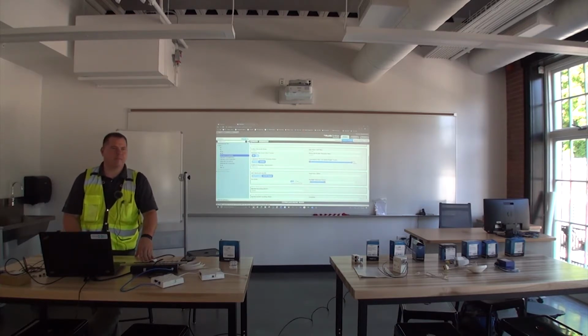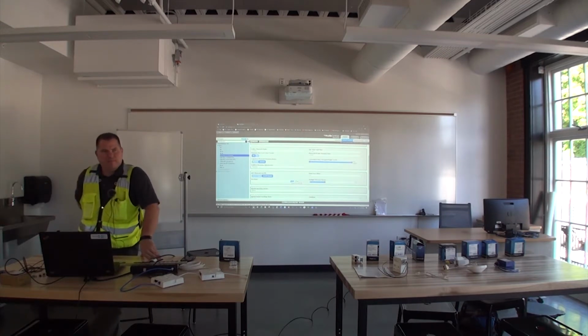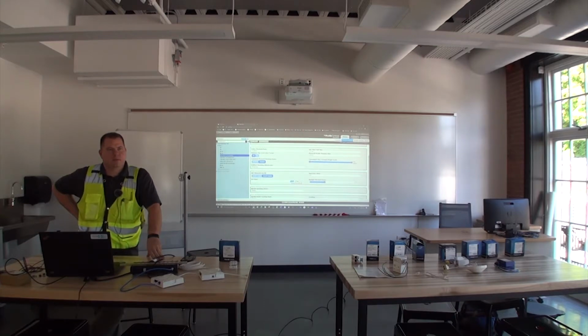Over in the library, it's the same system — yes, light harvesting. I know they've complained that whenever it's daylight, it still gets too dim for people working and reading, even next to the window. That's because that space was set to 30 foot candles, which is really dim for a library. This is where you fix that. I have a feeling this library is also probably going to run at full rate. Yeah, there's a commissioning agent — I can't change it until they sign off on it.